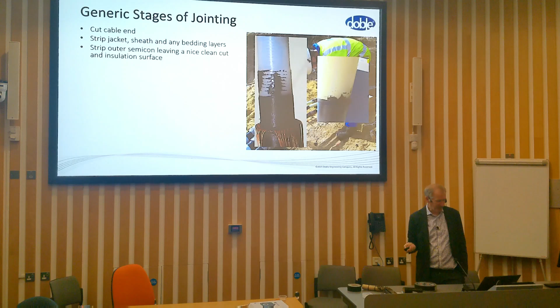Then you're going to join the conductors together. There are different ways of doing this. This is a shear bolt connector - you have the two pieces of conductor, and the connector goes over the top. You crank the bolts up and they shear off at a certain force. In the old days it used to be done with a torque wrench, relying on the jointer being very skilled and following the instructions. Now you just ratchet it up, get the right tension, and the bolt shears itself off.